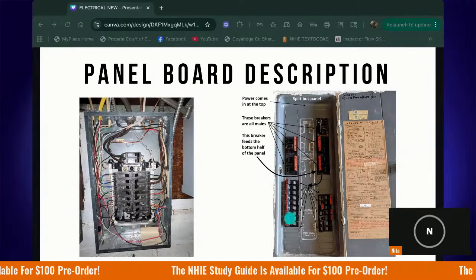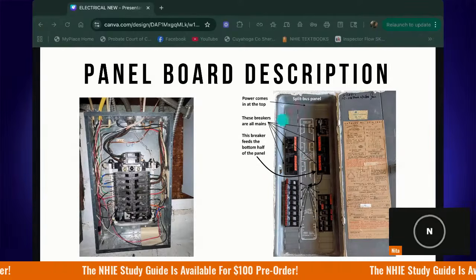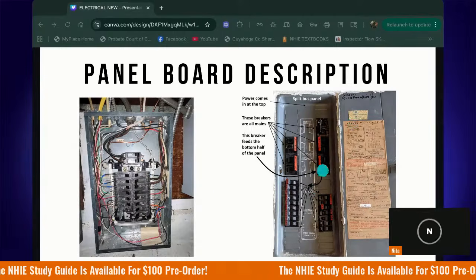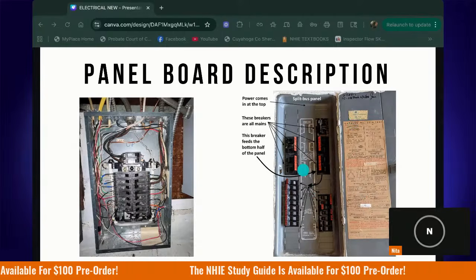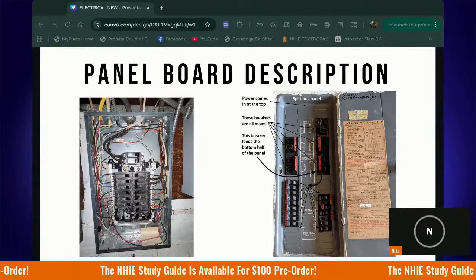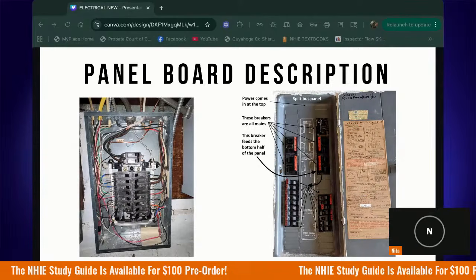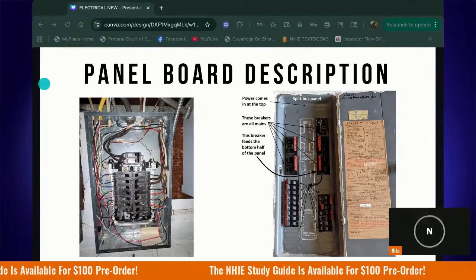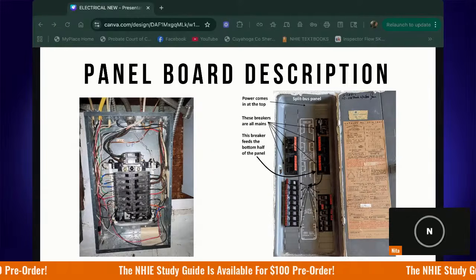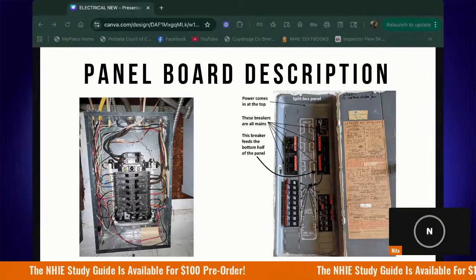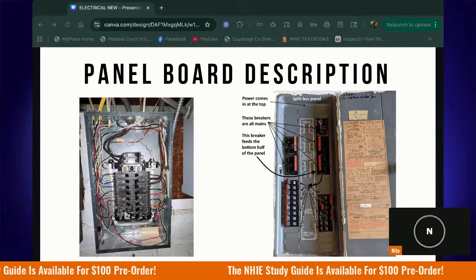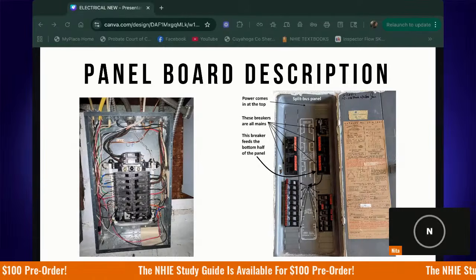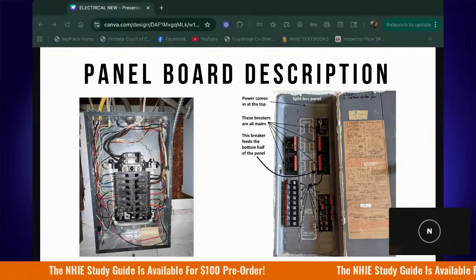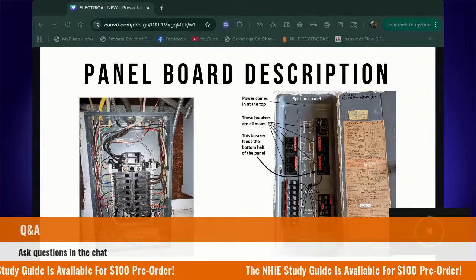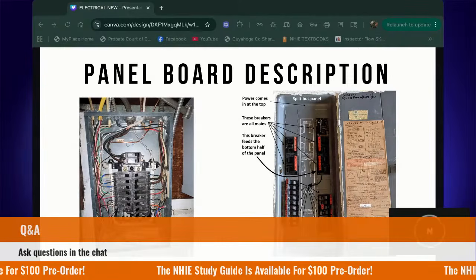Because they are sub panels, inside of the sub panel, neutrals must be isolated from the grounds. Write that down. You may not understand it right now, but you need to know it. In a sub panel, neutrals and grounds must be isolated or separated. Neutrals and grounds must be isolated and separated in a sub panel.